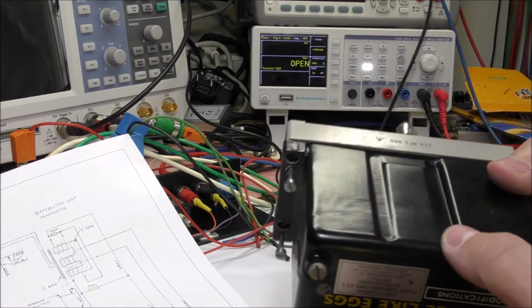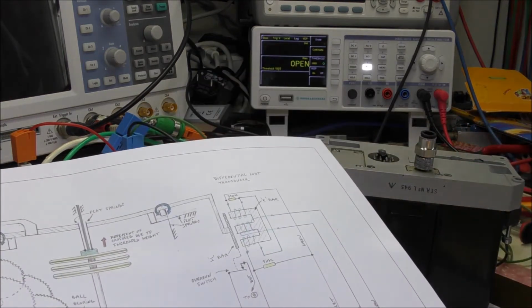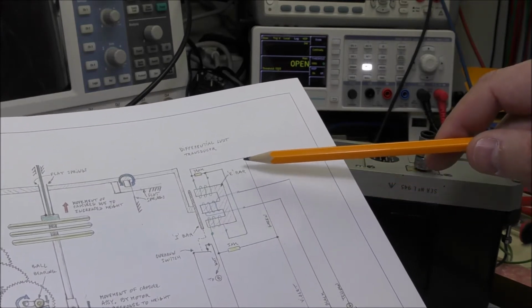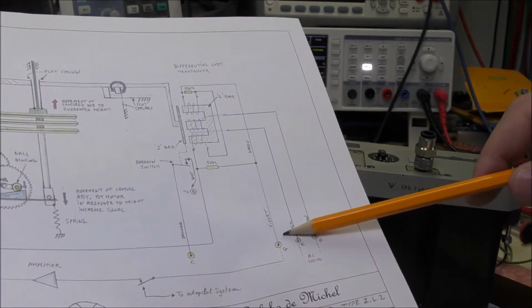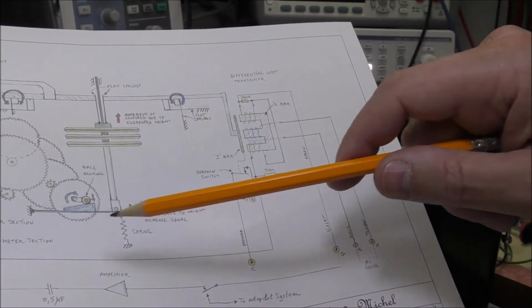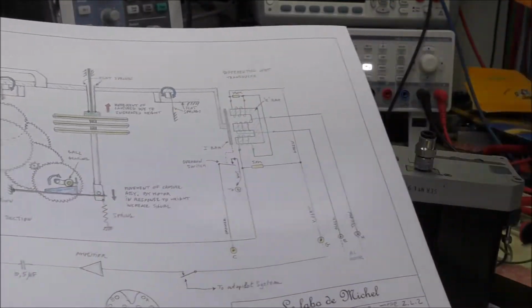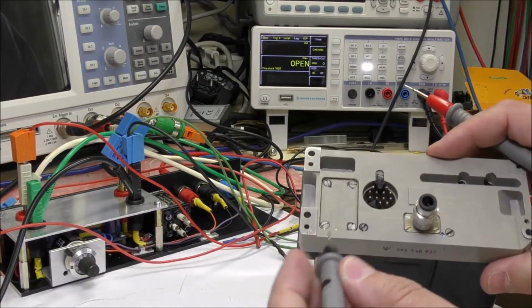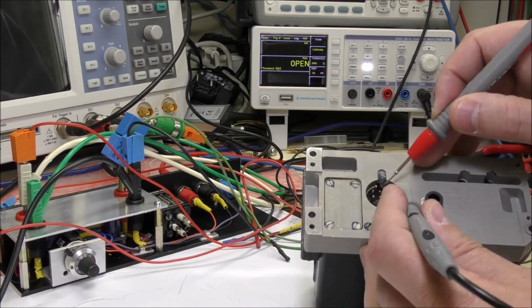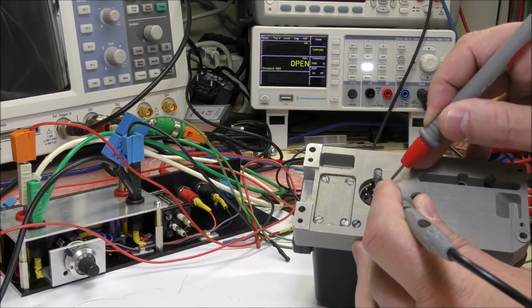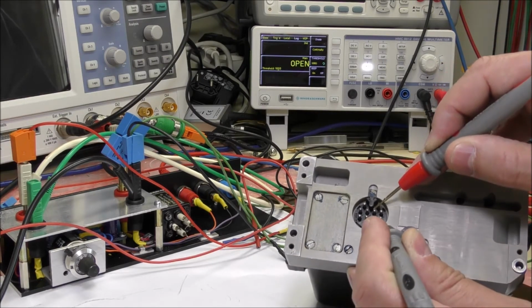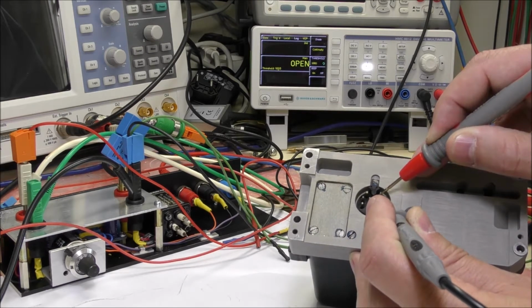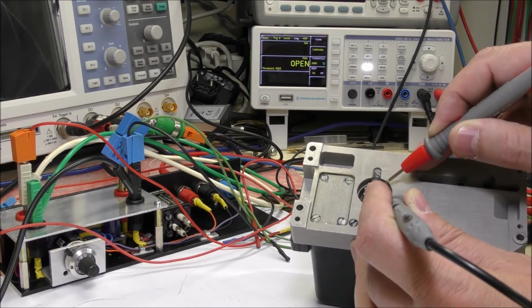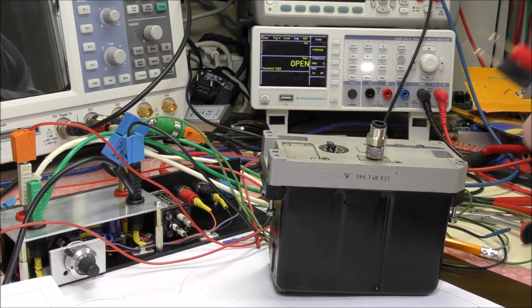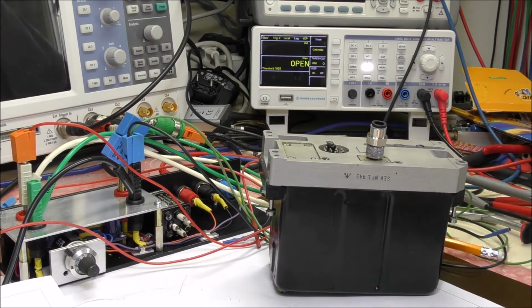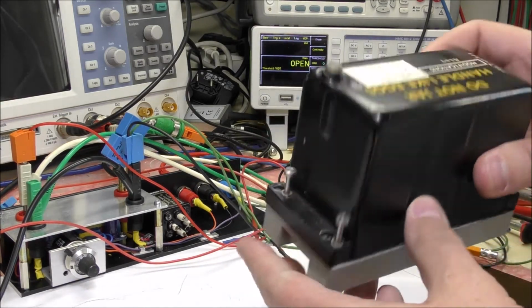This one doesn't seem to work. It is supposed to have a resistance between the measurement coils here and the tachometer, between the terminal G here and the terminal D. But when I measure with my continuity tester between D and G, which is just here, there is nothing. So it's open circuit, so I think there is a problem inside. So the only problem is the measurement of the LVDT or the tachometer also. So we need to open this thing.